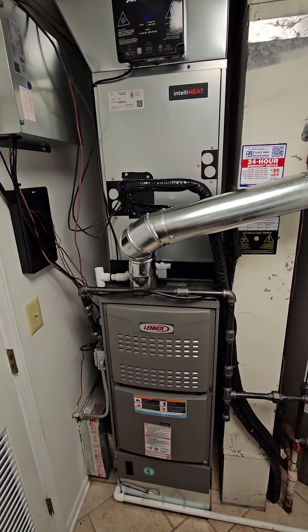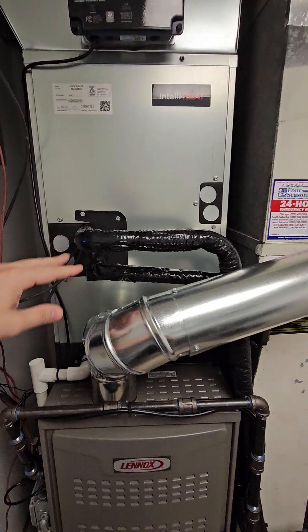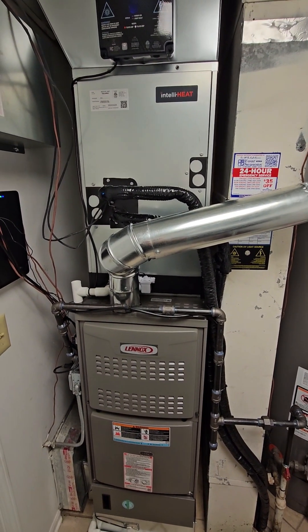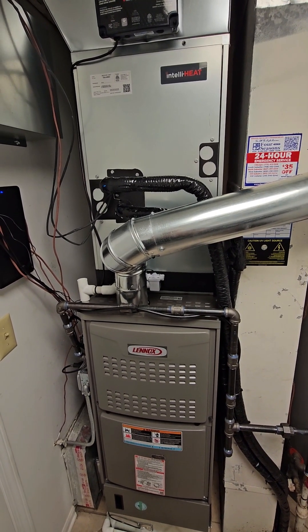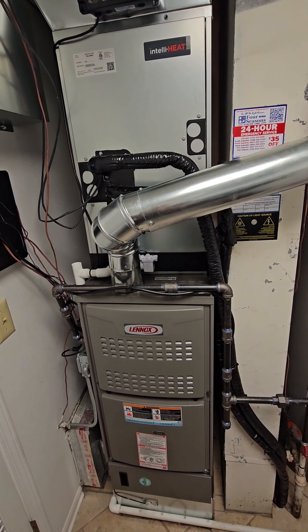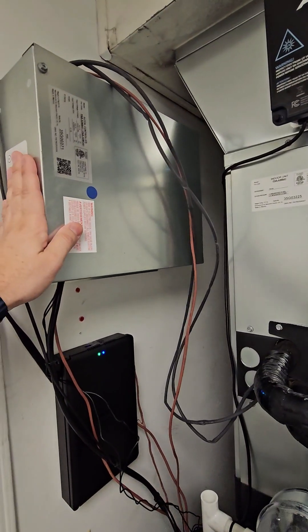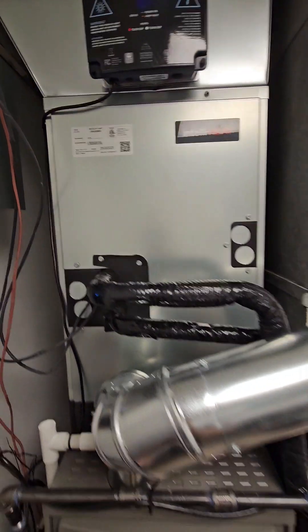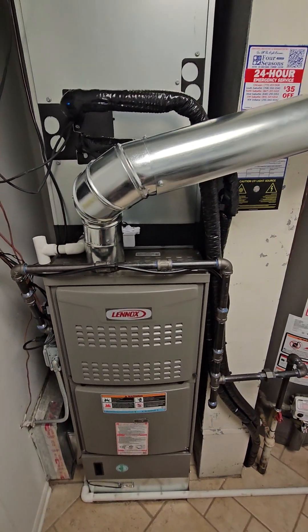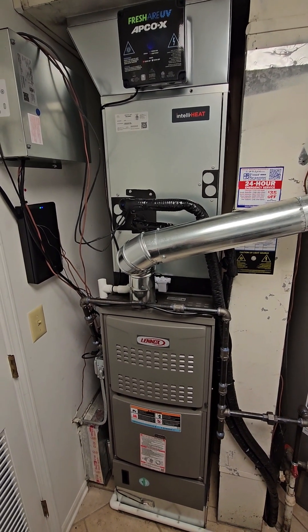The way this works: we have our outdoor unit — the heat pump — and because it's a heat pump it can heat or cool. Via the refrigerant line, that heat pump is going to be either warming up the coil in the winter instead of firing the gas furnace. Our outdoor unit will warm up the coil and all the furnace will have to do is circulate air through the ductwork to get heat into the home. We have our coil control box — it's a 3-ton system with a PAA-A36 coil matched to our 3-ton outdoor unit. The gas furnace is acting primarily as a blower and backup heating when temperatures get really cold. On average, seven out of ten days, the heat pump will be doing all the heating and the furnace will act as a blower.